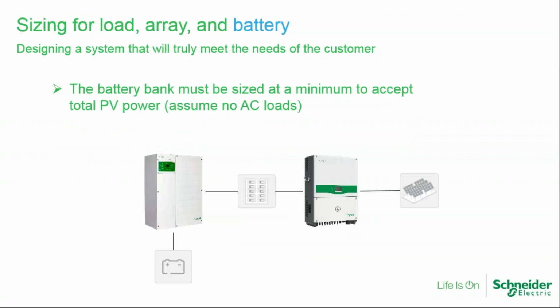Battery size is basically sized to accept the power. So some batteries are limited as to how much current they can take. And so if we assume no AC loads, and we have, say, 5 kilowatts worth of PV power, that is a significant amount of current that may or may not exceed the capability of the battery. So 5 kilowatts at 50 volts is 100 amps. And so if you only have one battery, like I say, people like to keep the battery bank size low, then that may exceed the capability of the battery. So that has to be factored in.